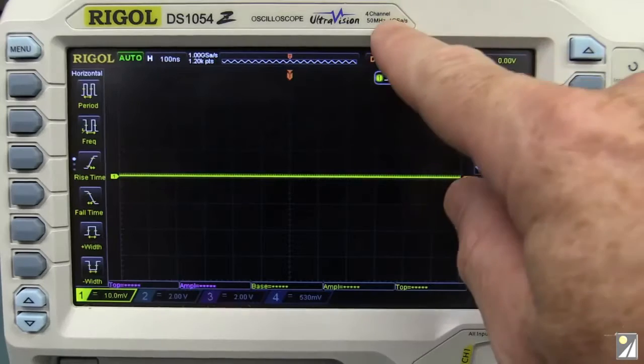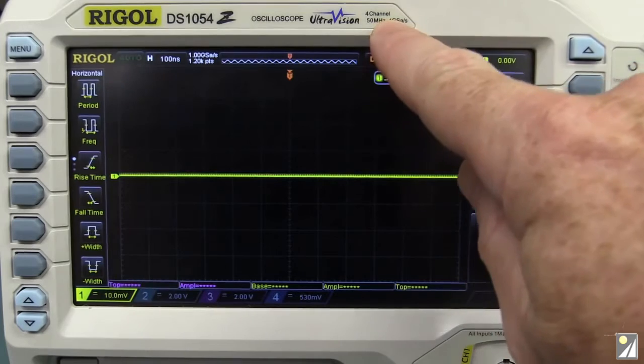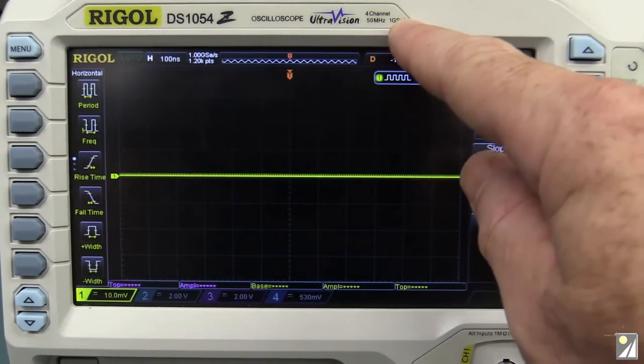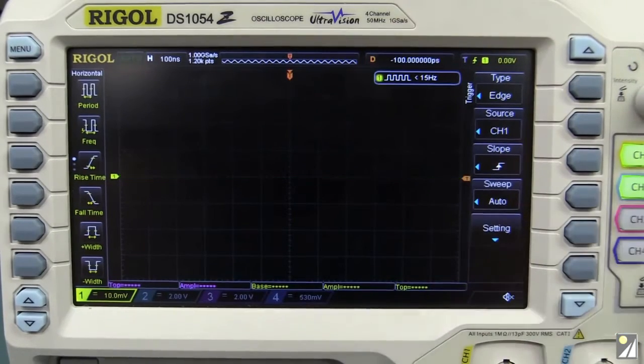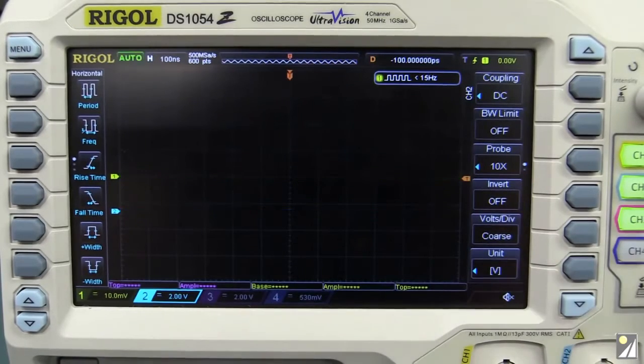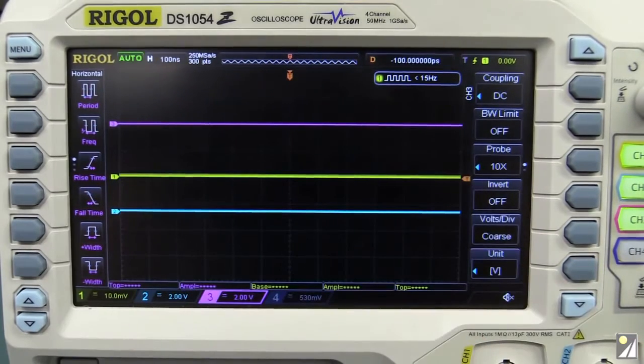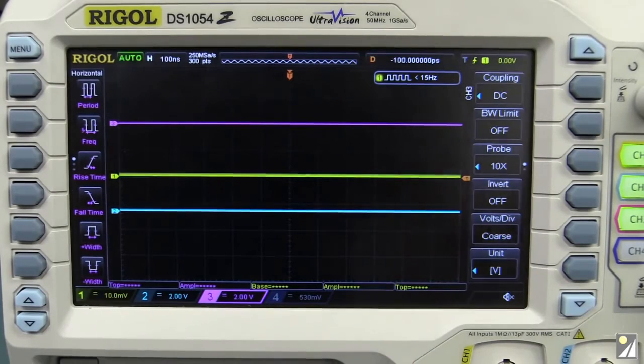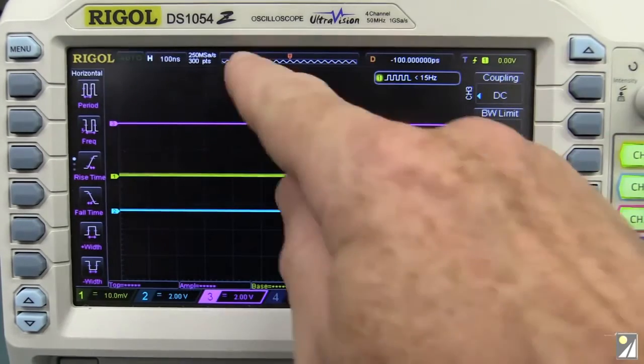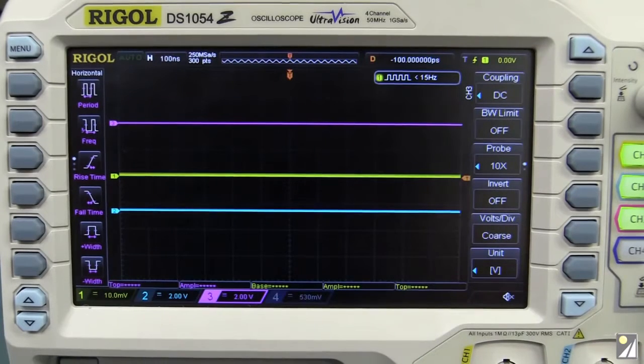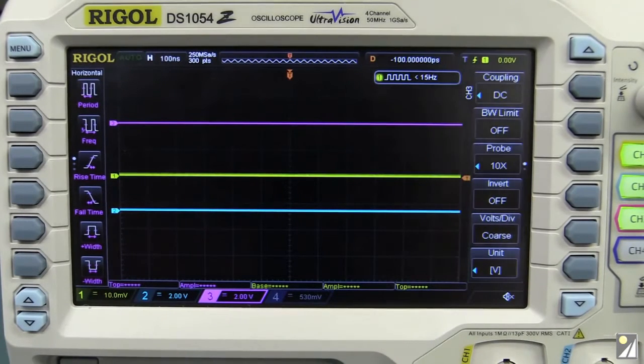This is a basic bandwidth of 50 megahertz. This is pretty good. And it's a reasonable one gig sample per second. But that is only for single channel like this. If you turn on a second channel like that, it halves to 500 meg. And if you turn on a third or a fourth, it drops down to 250 meg samples per second. And if you buy the 100 megahertz model, then 250 meg samples across all four channels is not the best. So don't expect the full 100 megahertz bandwidth when you've got all four channels turned on.